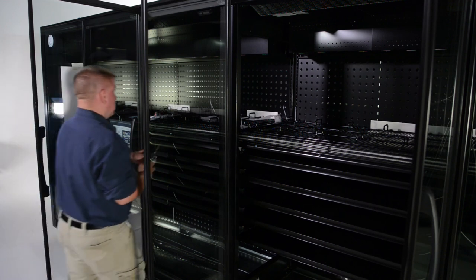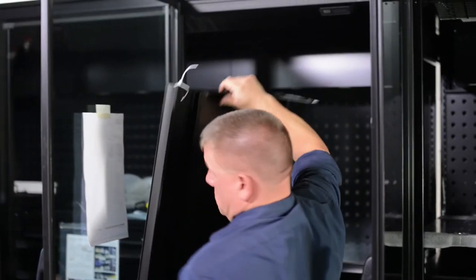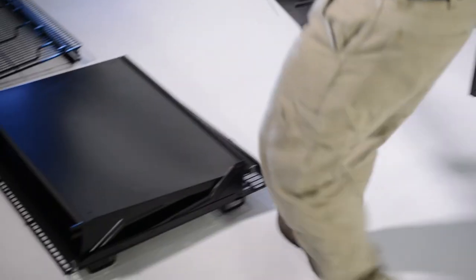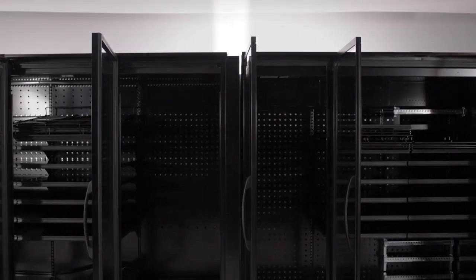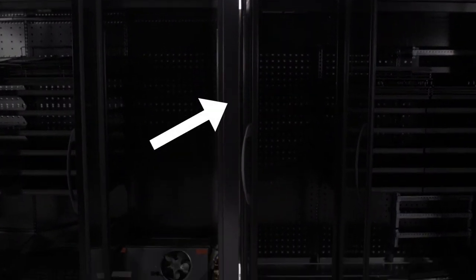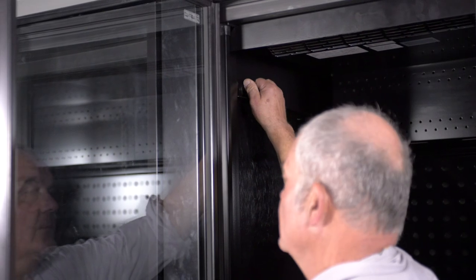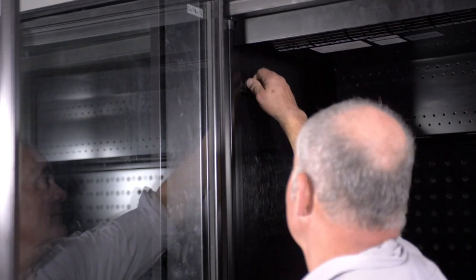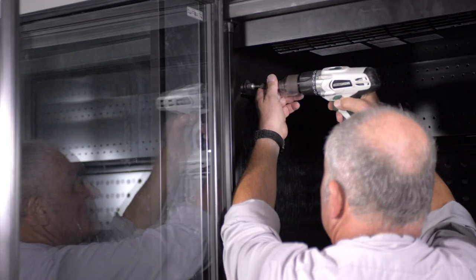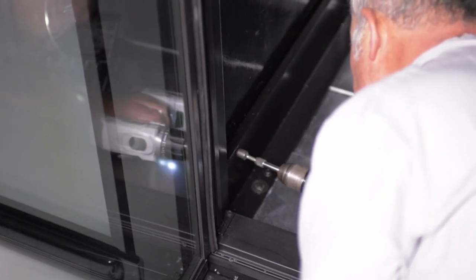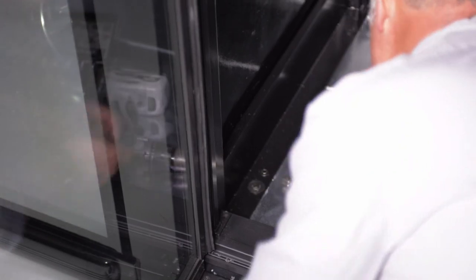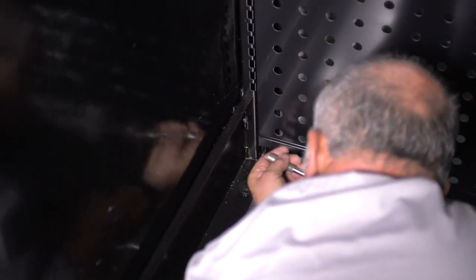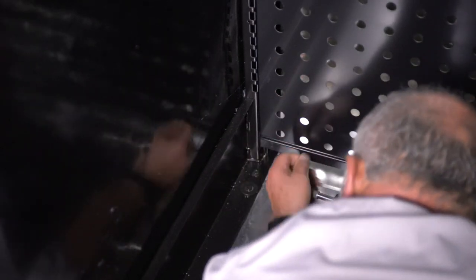Prepare the cases to be joined by removing the shelves nearest the ends that are to be joined. This will allow access to the case end frame bolt holes. In this freezer to cooler installation, an insulated divider has already been installed on the unit at the factory. Insert the provided 3/8 inch hardware and tighten the bolts while pushing the cases together. This draws the cases together and secures the insulated divider. Do not use the case bolts alone to pull the cases together.